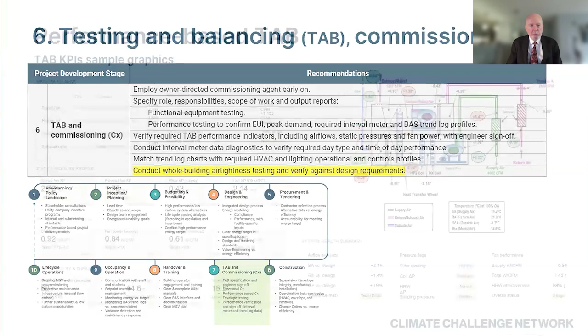So here we're going to call this performance-based testing and balancing. And it's sort of self-evident, but the graphic on the top right-hand corner there, your engineering team must look at this when these results come back and see what's working and what's not. It's an overstatement, but it would be the vast majority of TAB reports that we see are highlighting really significant deficiencies within the installation that can be and must be corrected, or you can't get to the numbers we're looking at.